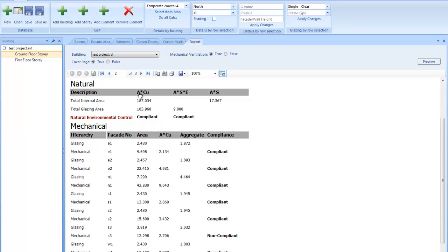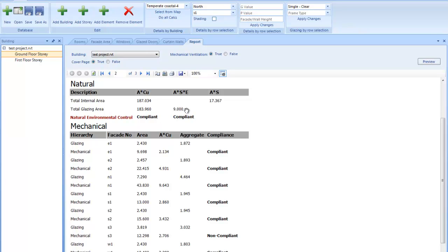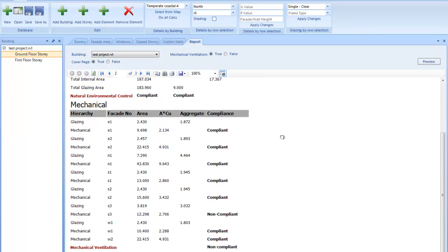Looking at the first one, here is your allowable conductance and solar heat gain. And these at the bottom is what you currently have in your fenestration elements. The conductance is less than that, so it complies. And the solar heat gain is less than the allowable, so you comply in the natural environmental control. So you would also look at the mechanical, if it's included at the top here.